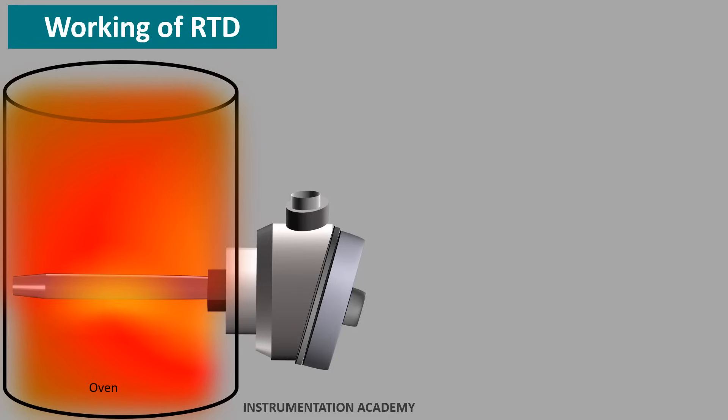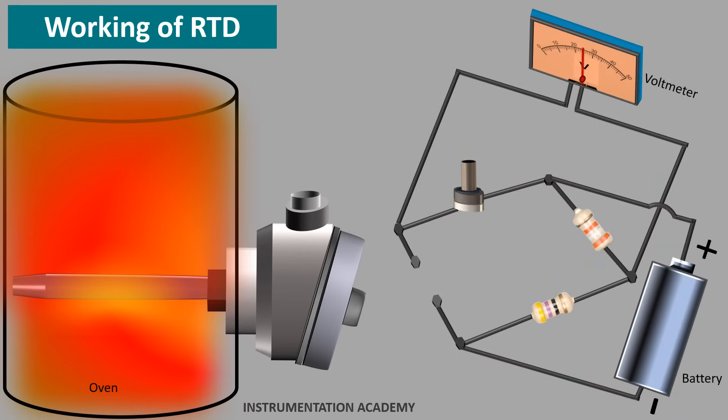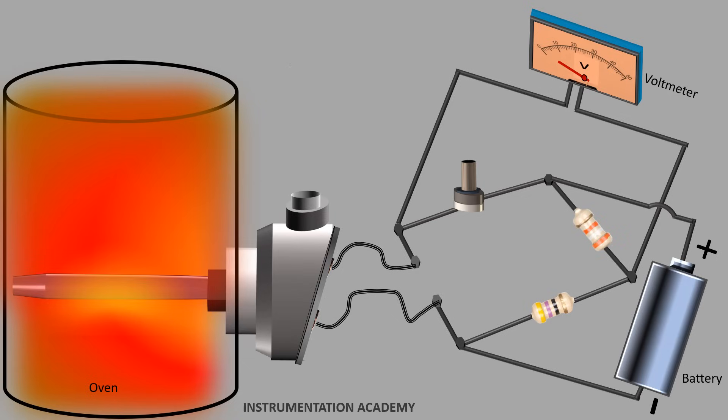So we have to convert that change in resistance to a change in voltage and this can be done using Wheatstone bridge. These Wheatstone bridge circuits are built into the transmitter, PLC, DCS or PID controller. RTD may be located hundreds of feet away from the bridge circuit.